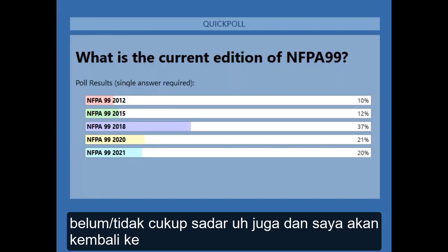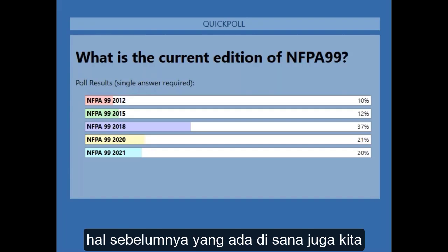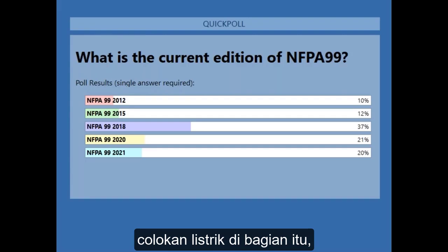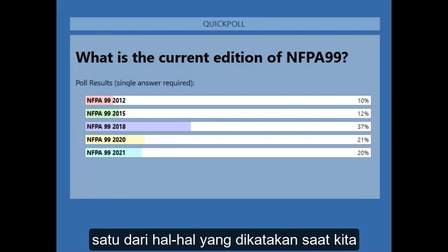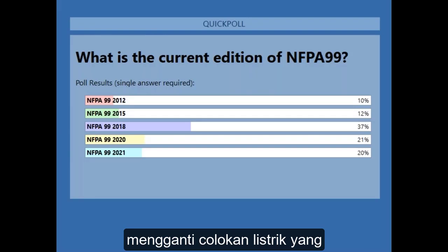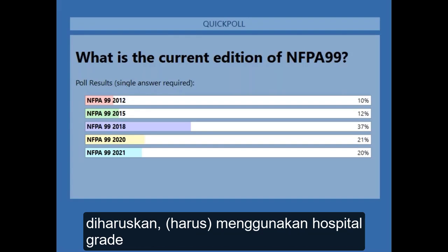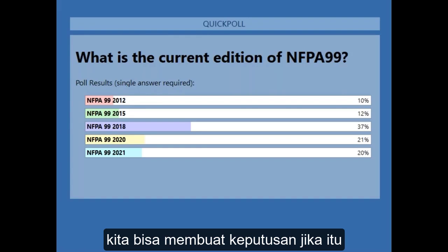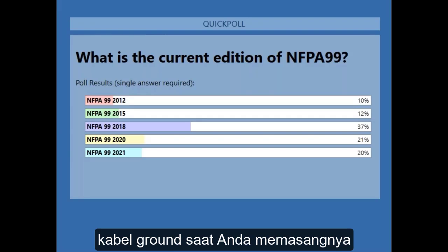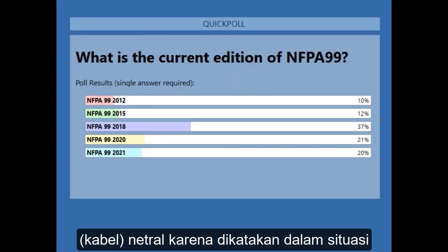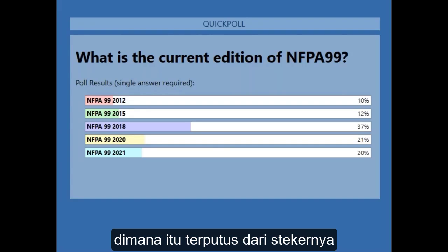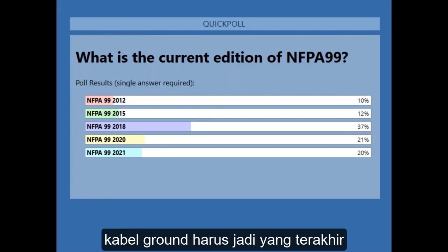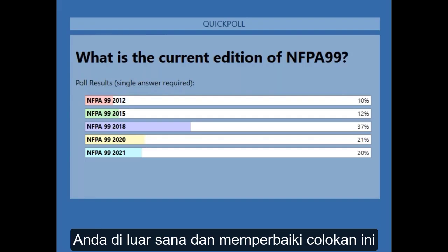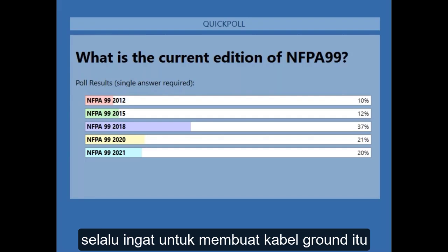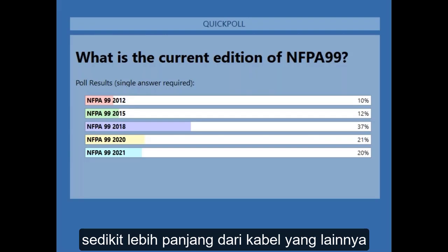Also, I'm going to go back to a previous thing. We talked about replacing power cords and power plugs. Well, within that section, one of the things it says when we are replacing power plugs, which is another change, is we're no longer required to use hospital grade. We can make the determination if it's a quality device or not. But one of the things required is that the ground wire, when you attach it, must be longer than your hot or your neutral, because in the event that it comes disconnected from the plug, the ground wire has to be the last one that becomes disconnected. So guys, when you're out there redoing these plugs, always remember to make that ground wire just a little bit longer than everything else.